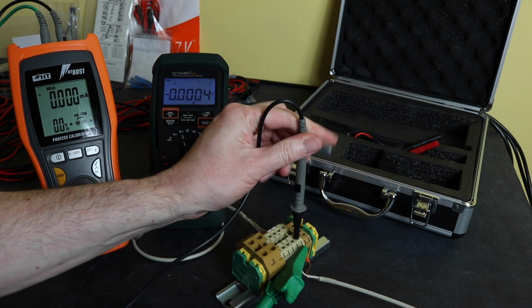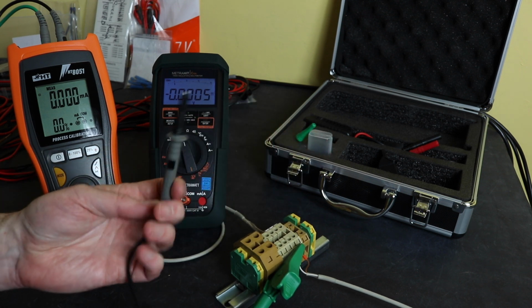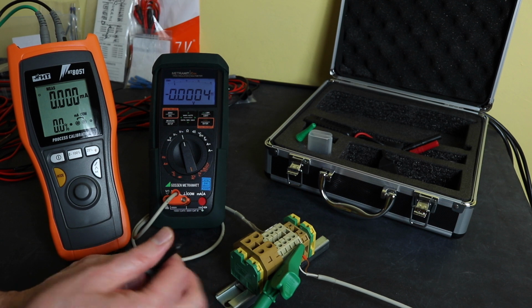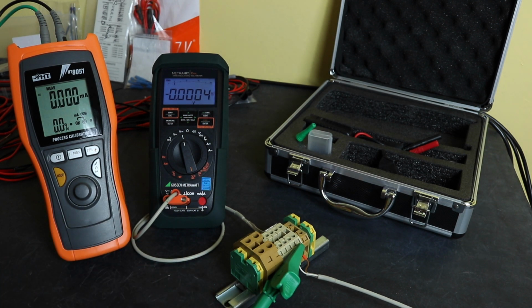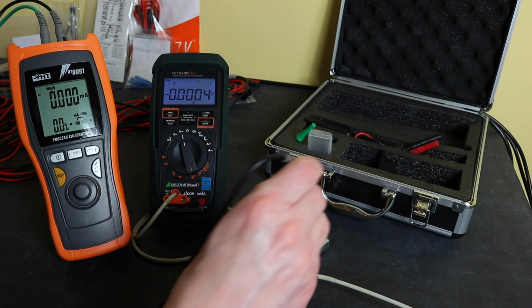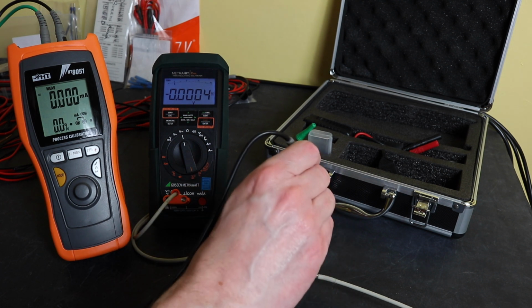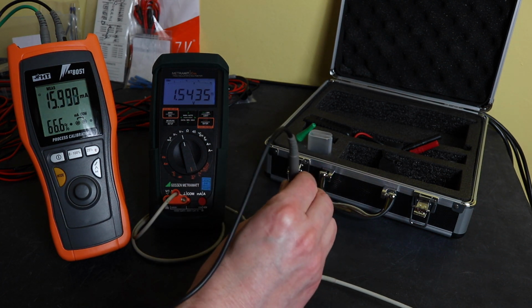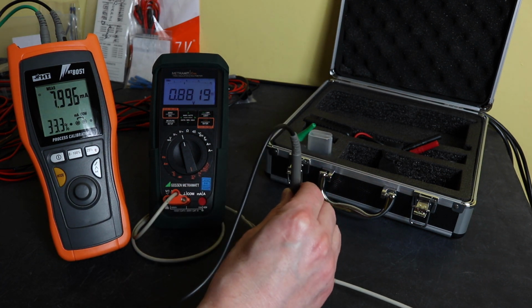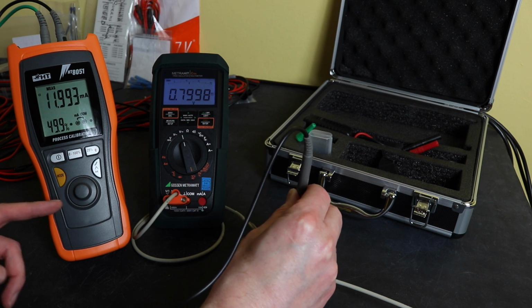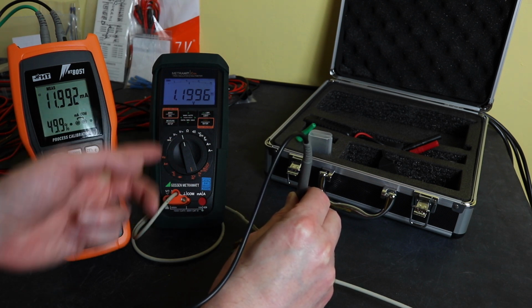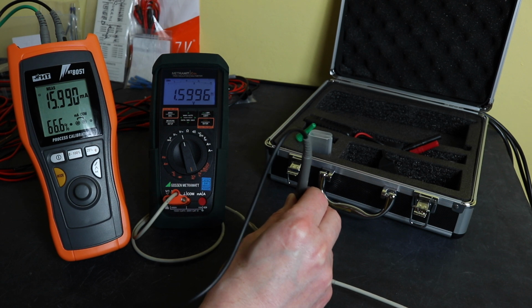But as you can see, these shrouds don't allow me to get into the type of terminals I'm used to. So if I just remove this, then with the shroud removed I can interrupt into the circuit, and you can see now I've got readings coming back. The current's being displayed here and the voltage is back being displayed on the meter over there.